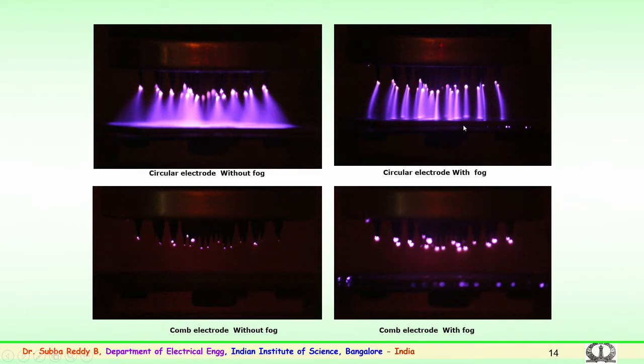discharges will completely change. Instead of a complete spread, you can see a very narrow type of discharges with higher magnitudes impinging on the sample. This is much more rigorous and of much higher magnitude in comparison to the normal conditions. So, this is again a similar pattern, which is being taken for the comb type of electrode.